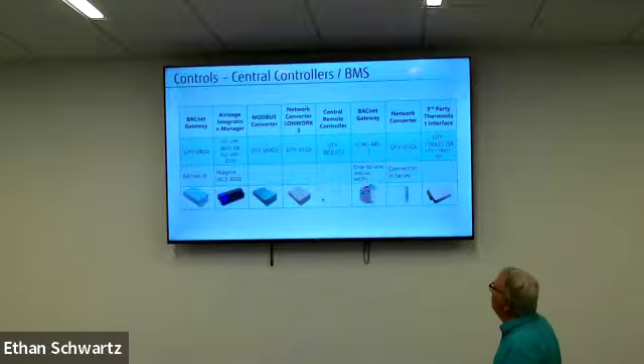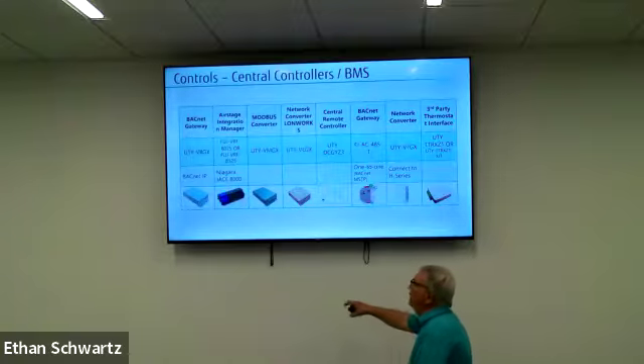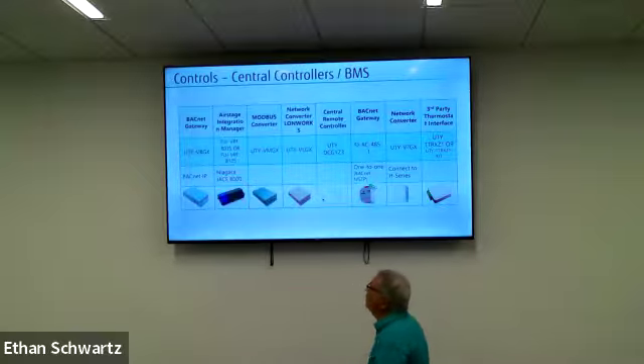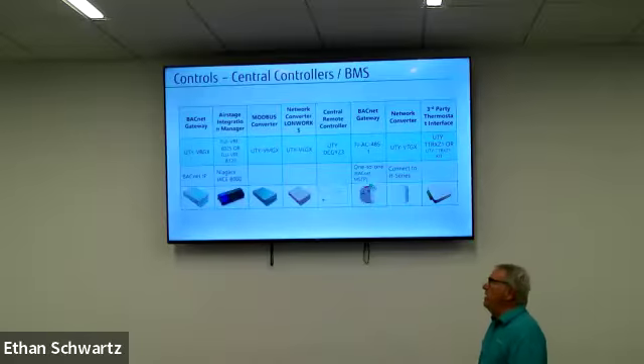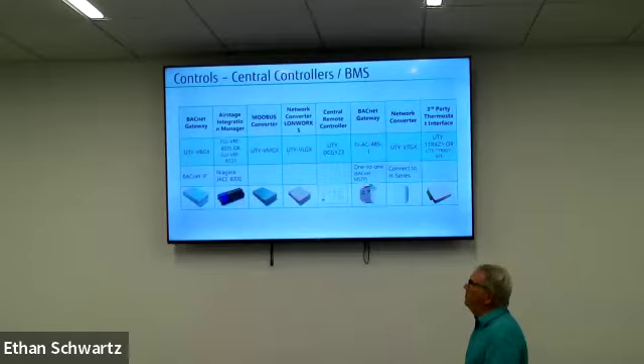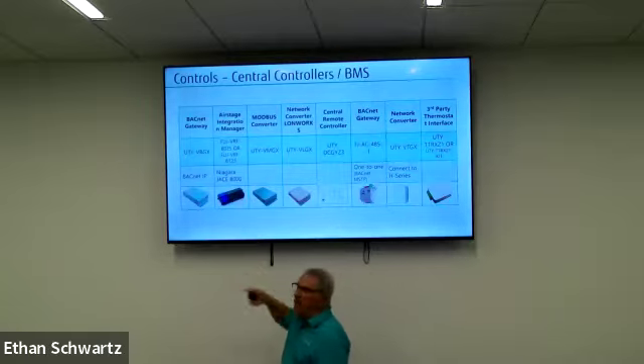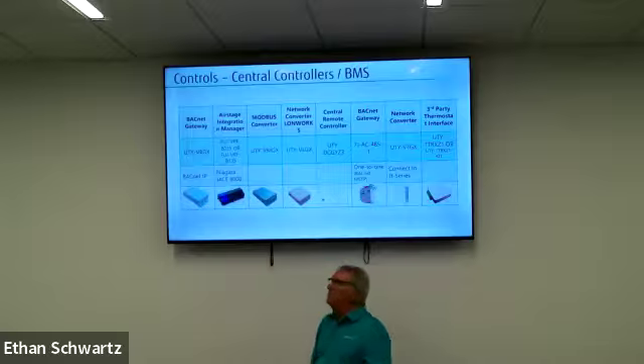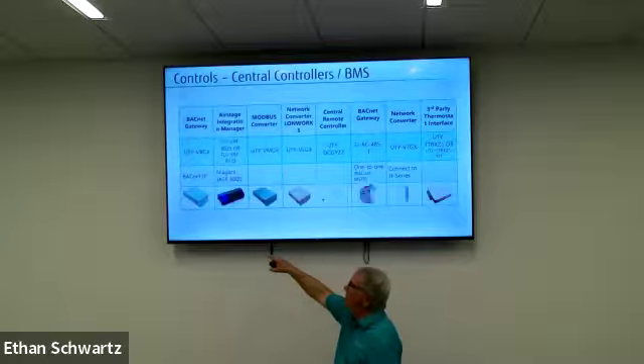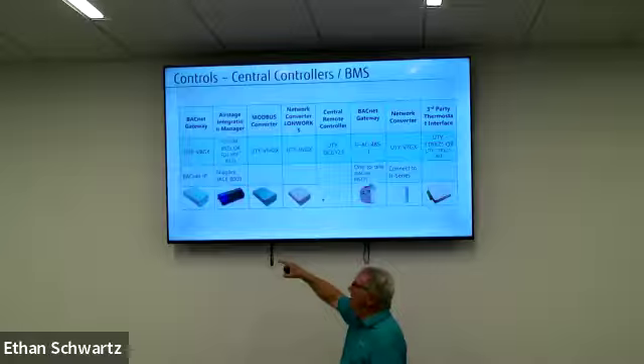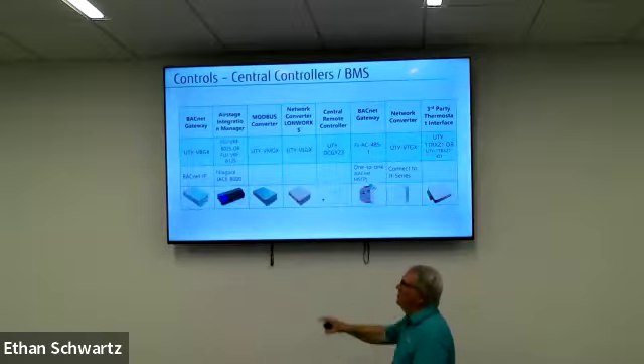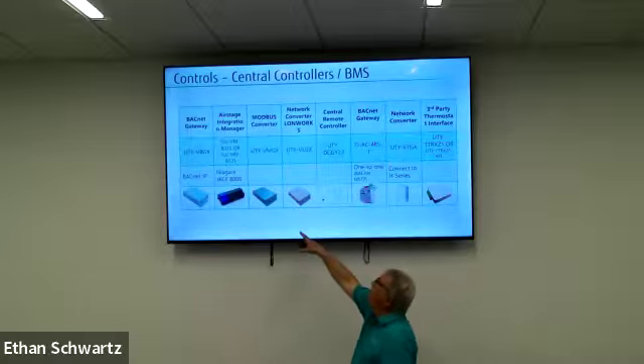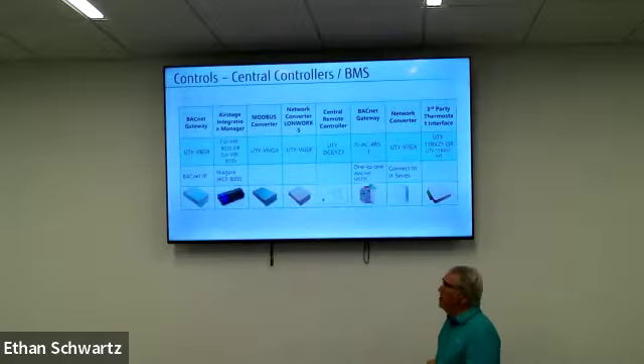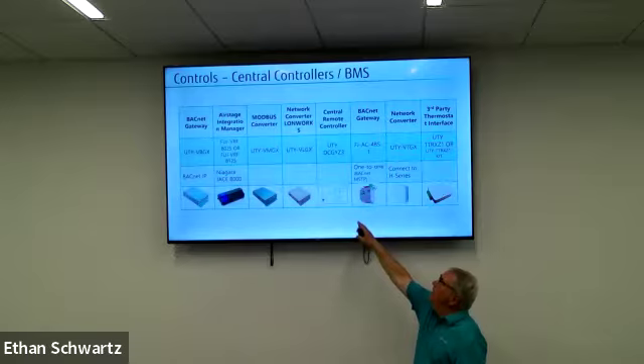So then we have, along with that, various controllers for larger projects, and some are for smaller. But if you have BACnet on a job, we use a BACnet gateway, a BACnet converter, and that would communicate directly on the BACnet protocol. If you have BACnet IP, or sometimes people will be using BACnet MSTP, we have another one on this slide that just came out earlier in the year that allows us to do BACnet MSTP, and I think also IP, so that probably that one will go away. Then if you have a Modbus control system or a proprietary LonWorks control system, we have those adapters. We have the central controller that I mentioned, the DCGYZ3.